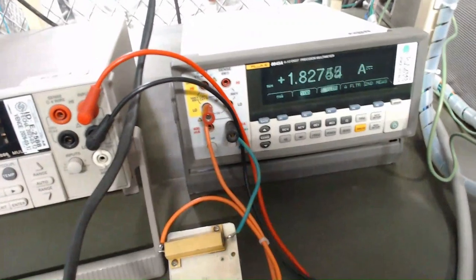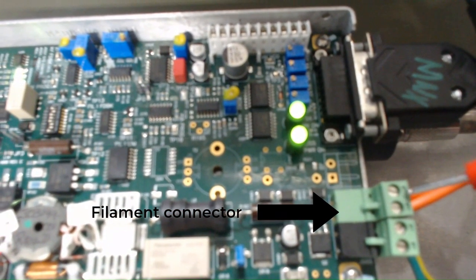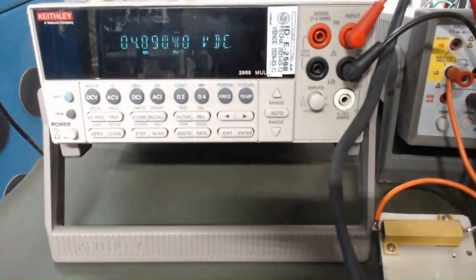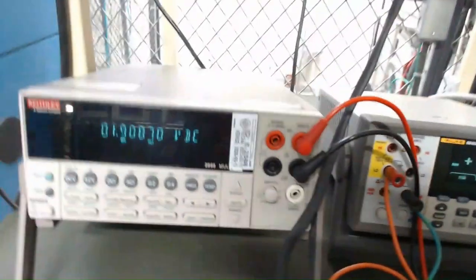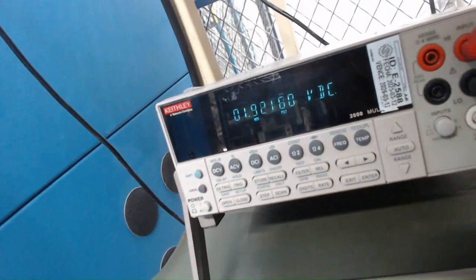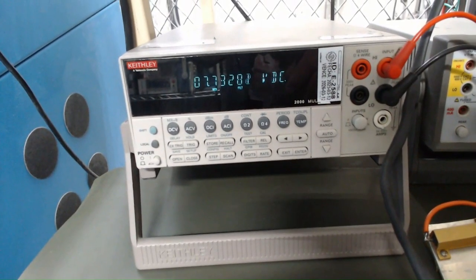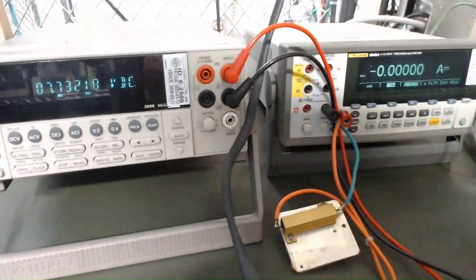For the filament voltage limit test, filament limit setting will be set at 1.8 amps, and then the filament load will be opened, measuring the voltage across the filament connector. Filament voltage should limit between 7.5 volts and 8.1 volts. We can observe that filament voltage with the filament connection open limits to 7.73 volts, which is within specification. Value is to be recorded in the datasheet.